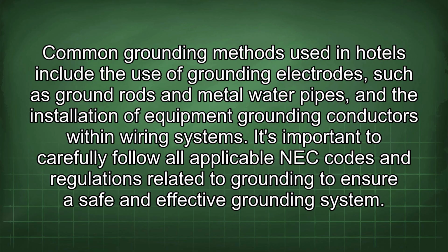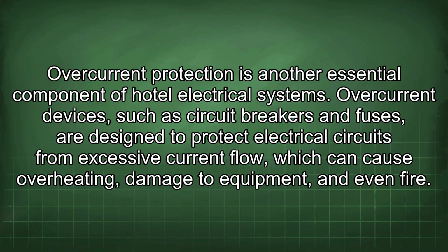Common grounding methods used in hotels include the use of grounding electrodes, such as ground rods and metal water pipes, and the installation of equipment grounding conductors within wiring systems. It's important to carefully follow all applicable NEC codes and regulations related to grounding to ensure a safe and effective grounding system. Overcurrent protection is another essential component of hotel electrical systems. Overcurrent devices, such as circuit breakers and fuses, are designed to protect electrical circuits from excessive current flow, which can cause overheating, damage to equipment, and even fire.